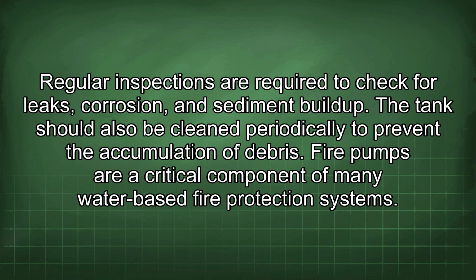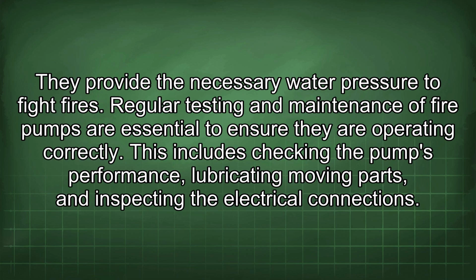Fire pumps are a critical component of many water-based fire protection systems. They provide the necessary water pressure to fight fires. Regular testing and maintenance of fire pumps are essential to ensure they are operating correctly. This includes checking the pump's performance, lubricating moving parts, and inspecting the electrical connections.